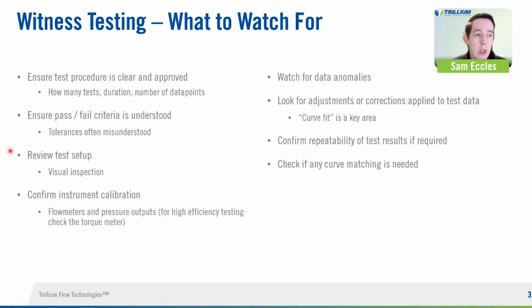From a practical point of view, in terms of reviewing the test setup, you should always walk the test setup, go around with the OEM, do a visual check, make sure there's a sensible number of straight lengths in front of and after the pump, check where they're taking pressure measurements, check where they're taking flow measurements. These things are very, very important. It's also your only chance to visually check that the equipment is free of leaks, contamination before the thing started.